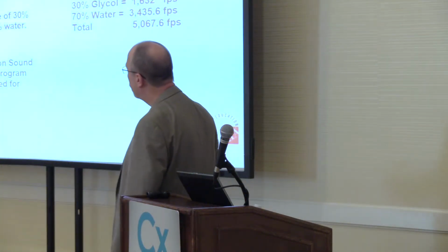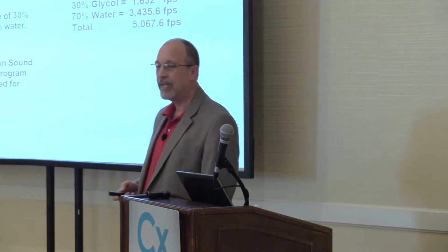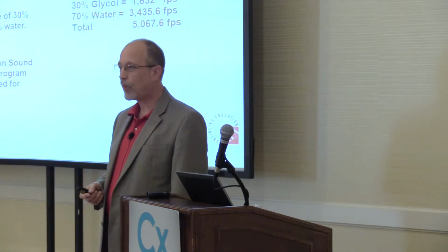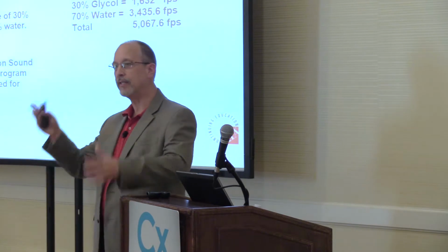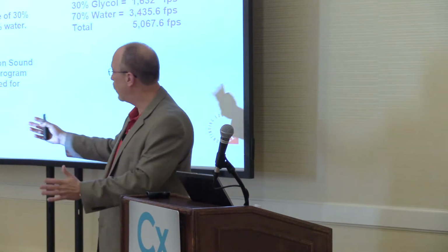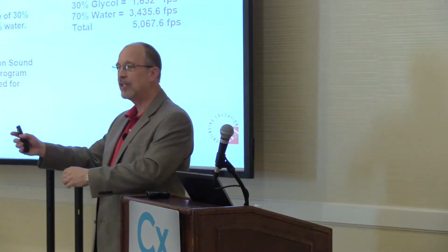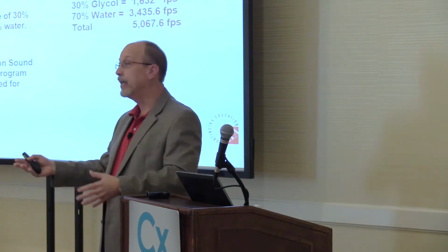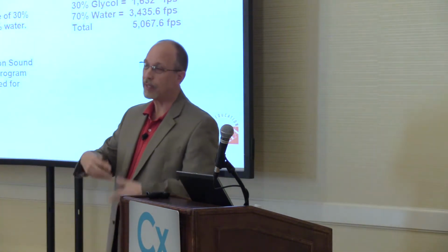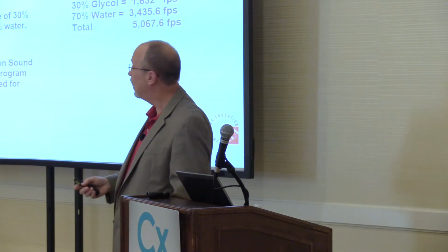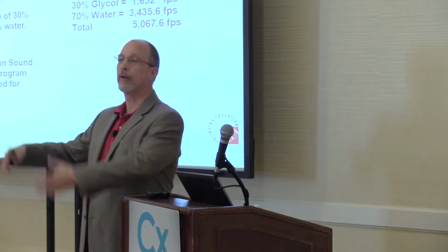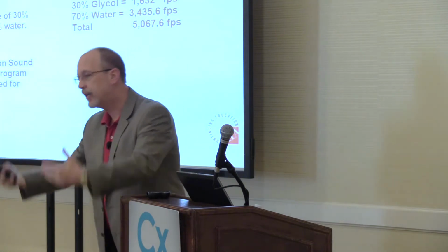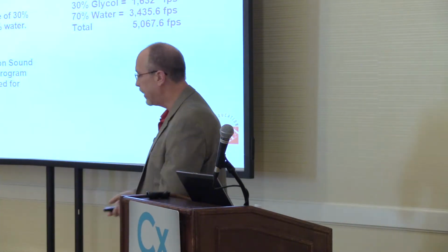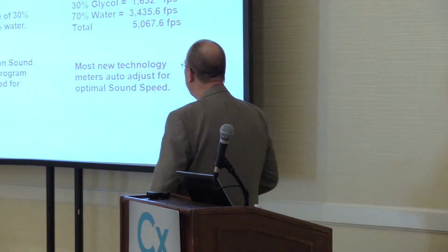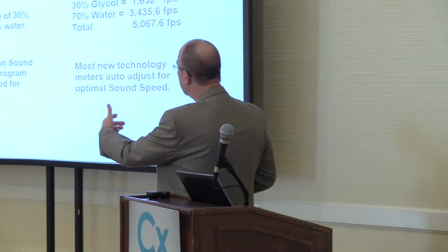Today, with most of the newer flow meters, if you're plus or minus 10% of the sound speed, the autopilot on it optimizes it up or down. So 20 years ago, if you were off a little bit on sound speed, it didn't work. And today, it's lazy man time. In this case, for this flow meter, I put in water and it'd figure it out. So the technology continues to get better. It continues to make it more efficient for you to work with it. Some of the older models don't have this feature, but they're all going in this direction.